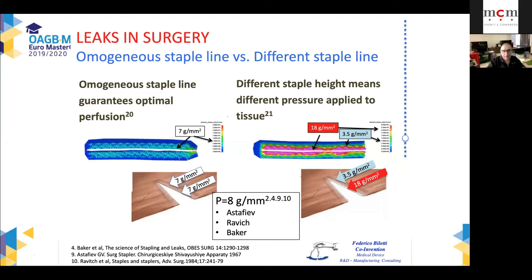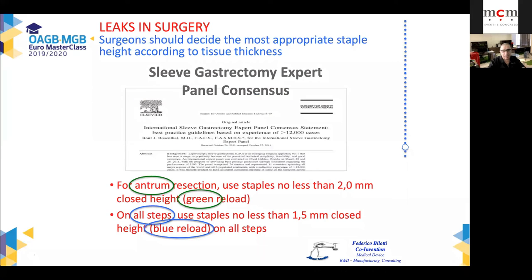But why limit yourself to looking at the tissue near the cut? You should also consider the fact that inside the patient, if the staple line inside the patient is bigger and larger, you have lower pressure applied. 3.5 grams per millimeter square is so low that you could have leakage inside the patient, bleeding inside the patient, and you don't notice it because you're only looking at the outside staple line, the only visible staple line.